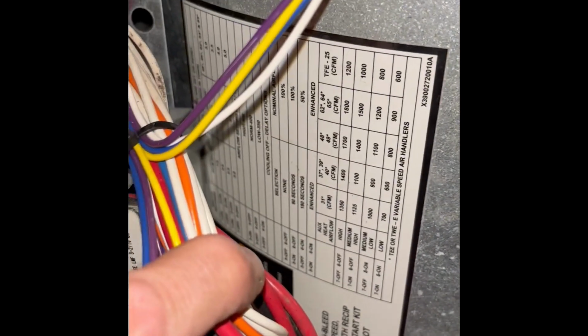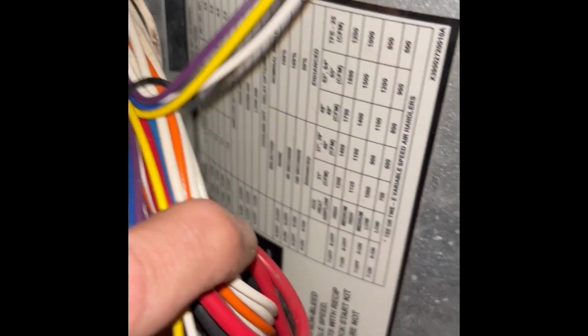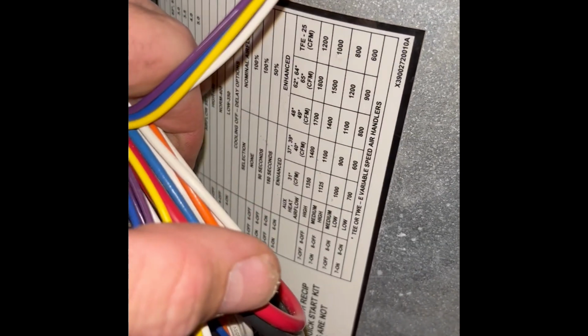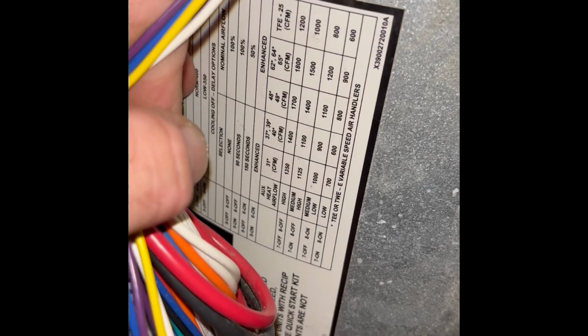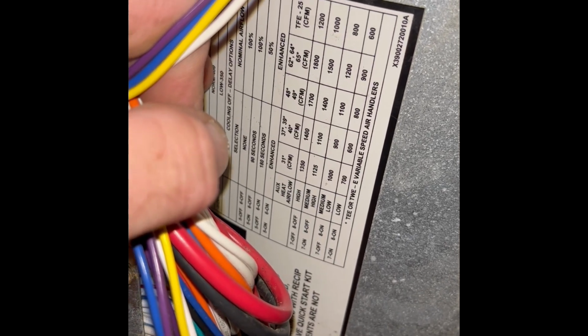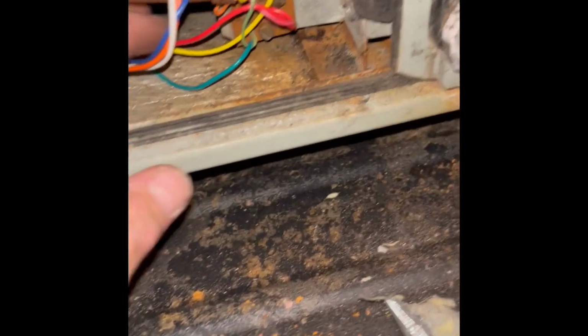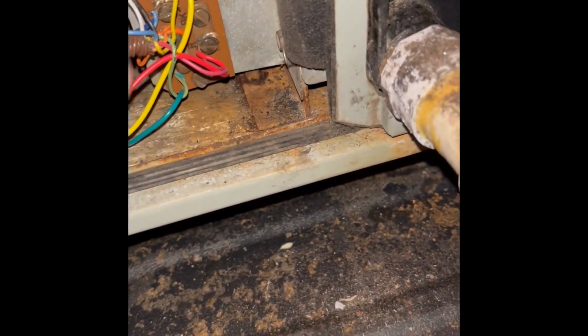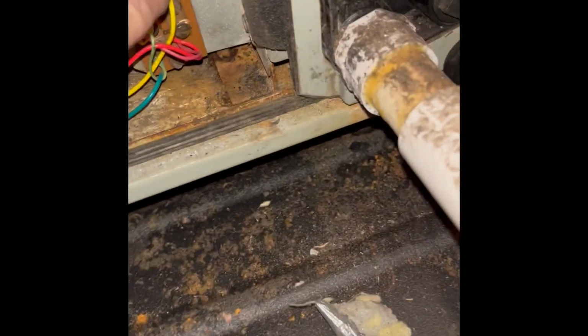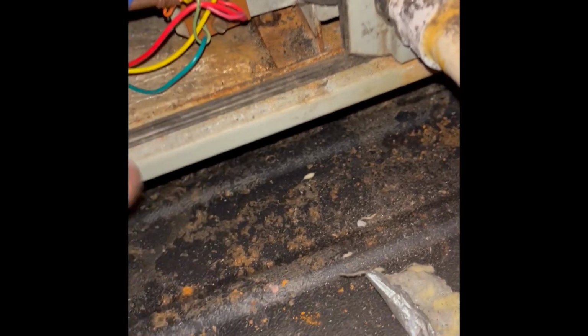We're looking at 3 tons, 400 CFM per ton, and I did turn the enhance mode off, so it's not going to send a varying signal to the blower. We just want our full speed blower the whole time. It is a single stage unit, so we're actually using Y2, which is our yellow wire, on the Y signal. Our violet wire would be Y1, which we're not using because we always want it to run in high stage because it is a single stage unit.